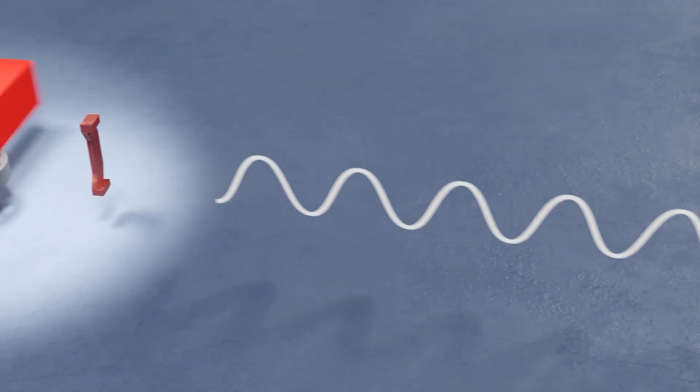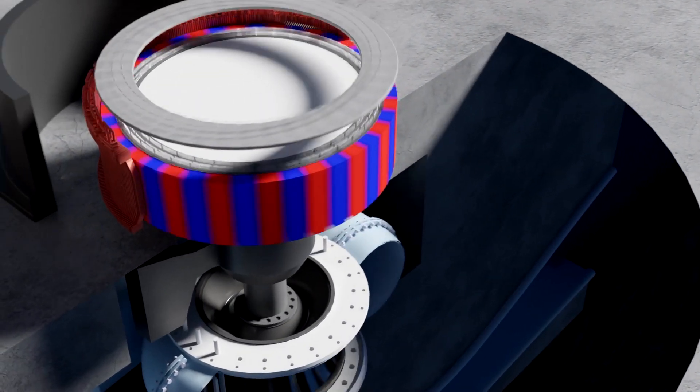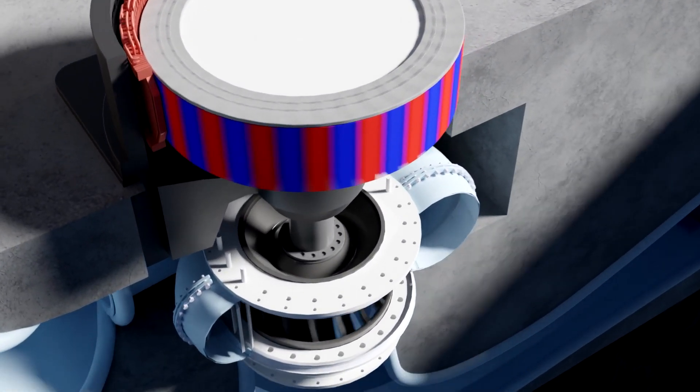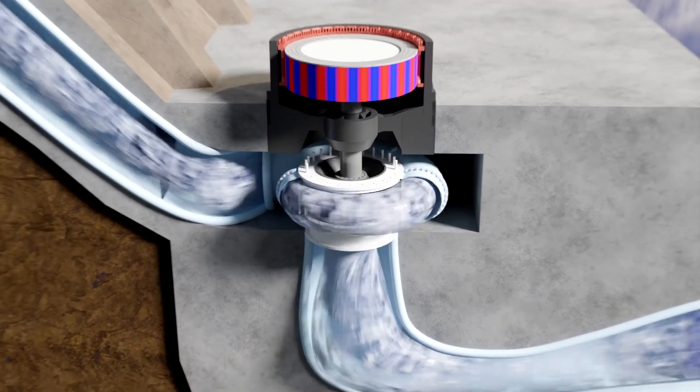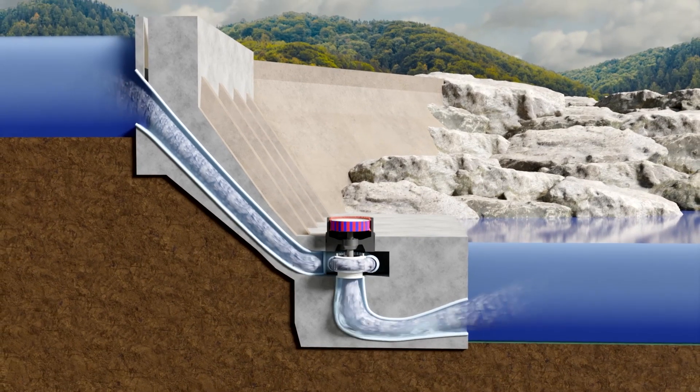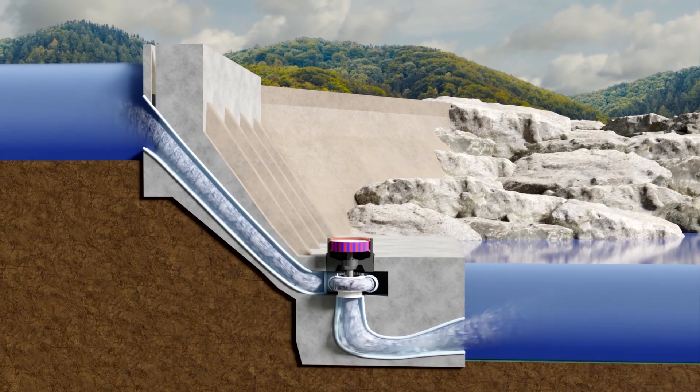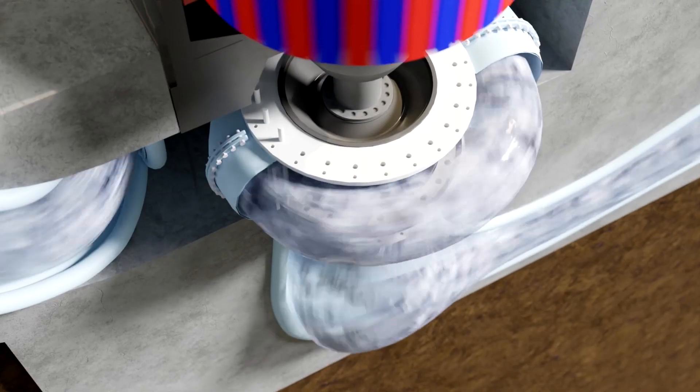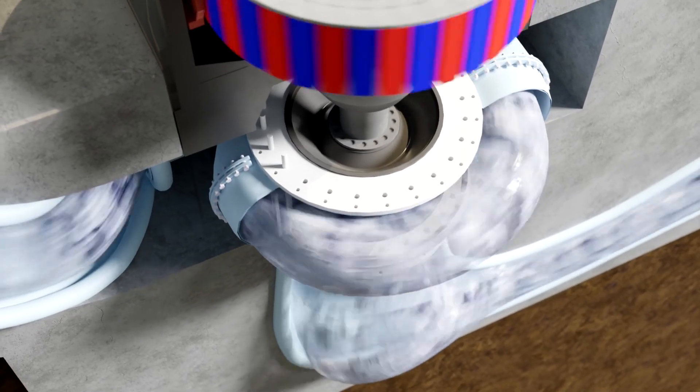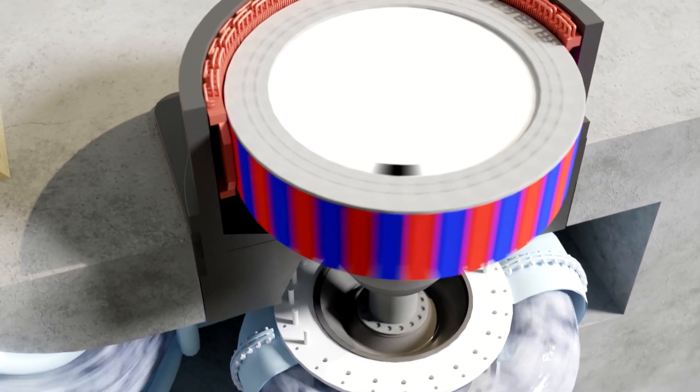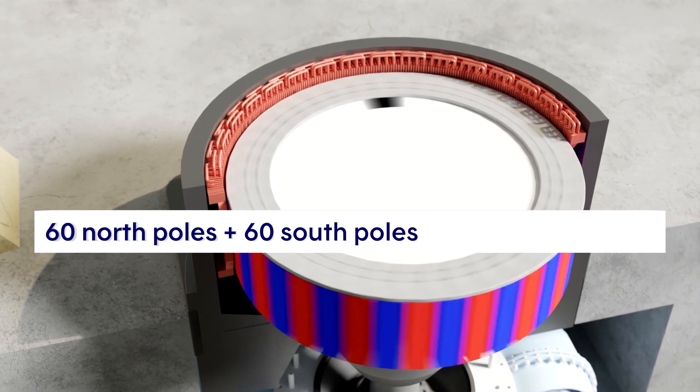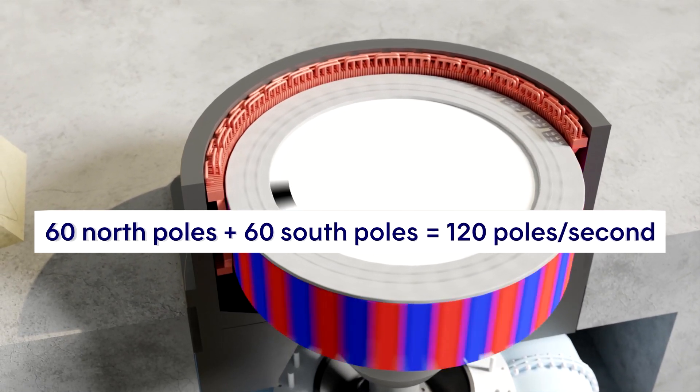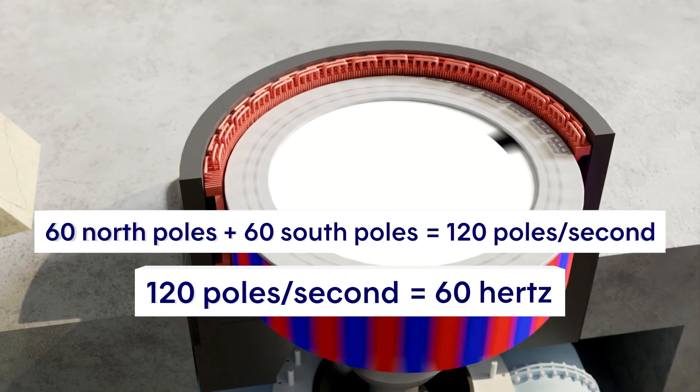But what determines the speed of the rotor? In hydroelectric generating stations, the rotors are activated by hydraulic turbines. For water to transfer its energy to the turbine, it must fall from a certain height. This is called the hydraulic head. The head determines the rotation speed of the turbine. The higher the head, the faster the turbine spins. For an electrical frequency of 60 hertz, each copper bar in the stator must pass both the north and south poles 60 times per second, for a total of 120 poles per second. So, 120 poles per second is equivalent to 60 hertz.